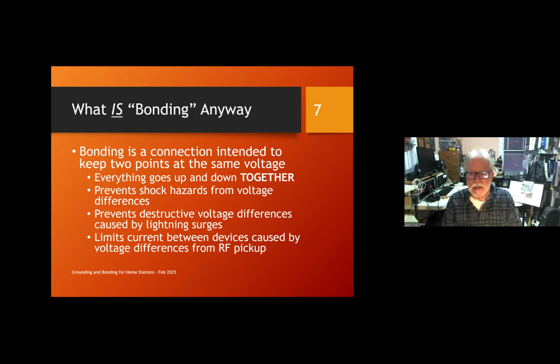So on the AC side of things, when you have everything bonded together, it prevents shock hazards and voltage differences. If you've got every piece of metal equipment in your station connected together, then you won't have one piece of equipment at, say, 115 volts because there's an insulation fault or something like that, and another at 0 volts with respect to your AC system. So that's a shock hazard. So by bonding everything together, you minimize that shock hazard.